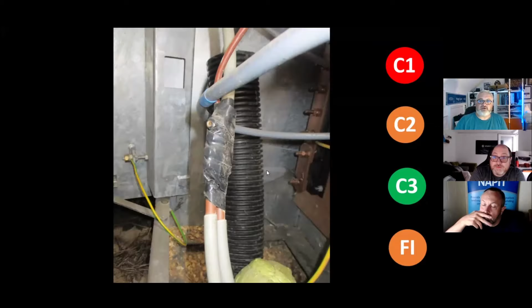C1. Just on that, Mr. Betteridge said the earth bar looks weird. They're a standard earth bar, a drop link earth bar. You can use a tool, it's got a hook on it, and you can disconnect the earthing conductor if you want, then connect your bonds and CPCs. Normally you get this crap from wholesalers or hobby homes, ask them for an earth bar and they'll send you those monstrosities. I'm becoming not a fan of them, just because they're exposed to the elements and corrosion, but we'll get onto that because we've got a couple.